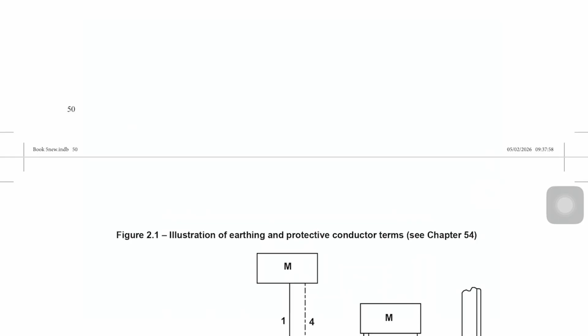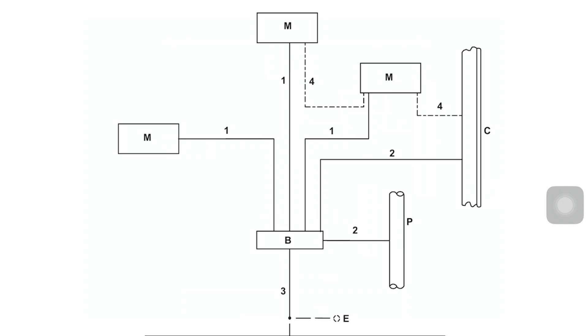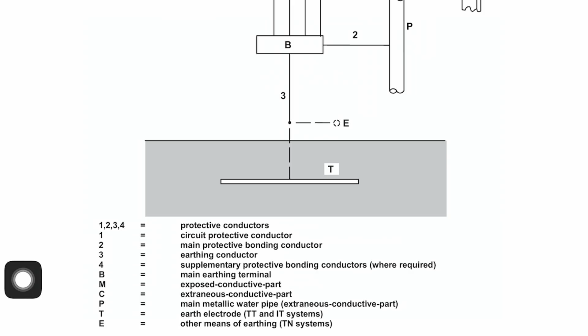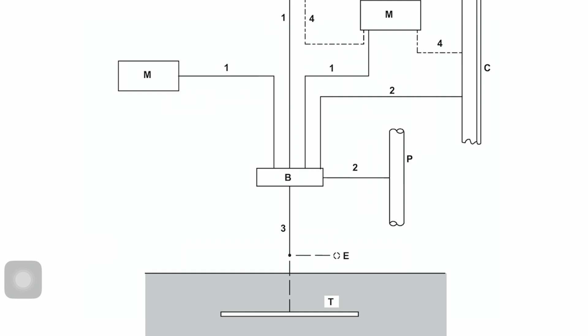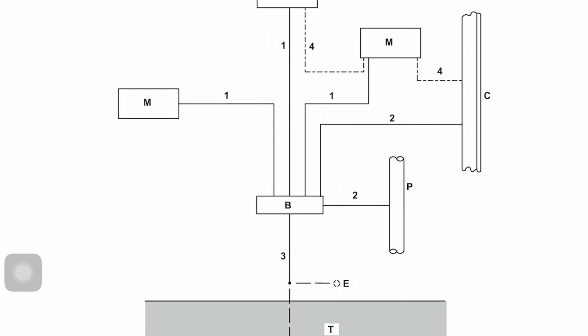And this is what I want to tell you. This picture here used to be very small. I managed to convince the IET to make this as big as possible, but the thing is there's only a certain amount of space on the page, so it was looking good with the image, but this text here was so small that most people couldn't read it. So do focus on this and make some little comments. I'd like to pinpoint B. B is the main earthing terminal. If you look at B down here, you'll see that it says main earthing terminal. Anything that's got M on it is a class 1 bit of equipment, and the number 1 should be CPC, which it is.